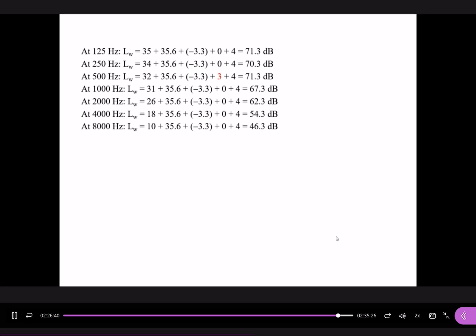Because we need to find the overall sound power level, we still need to consider other frequencies from 125 Hz up to 8K Hz. The only difference is at 500 Hz, where we need to apply the correction factor of 3 dB. For other frequency values, we do not need to make a correction—only at 500 Hz—because all other values are not within the range of 354 Hz up to 707 Hz.